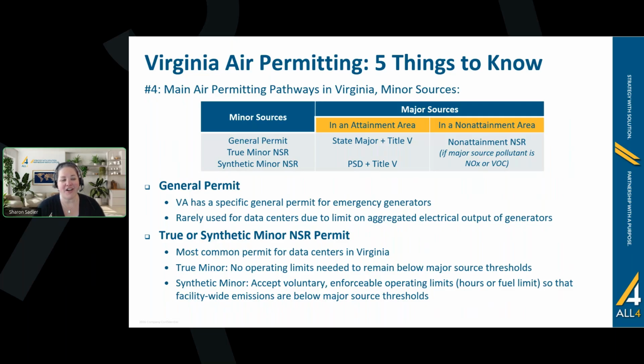And then you heard Harry talk about the minor NSR permit, the minor new source review permit. And you could have a couple different types of facilities in this bucket. You could not need operating limits to stay below the major source threshold. This might be very doable if you have an edge data center that has 4, 6, 7 generators, 500 hours. You might be below that 100 ton threshold, for example.